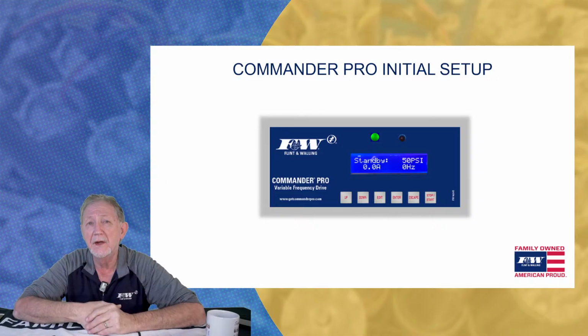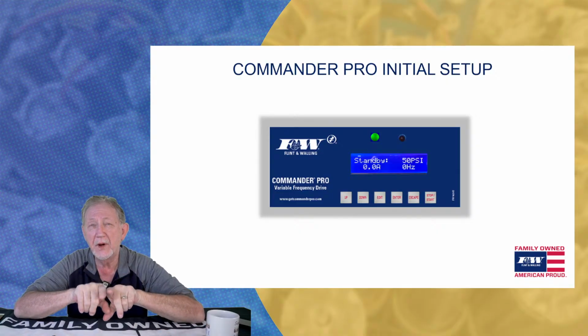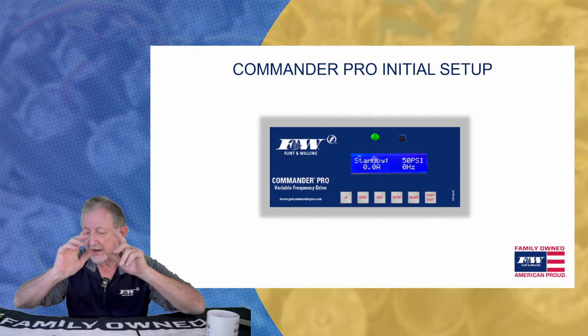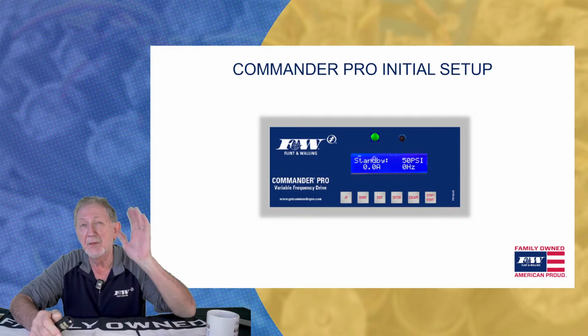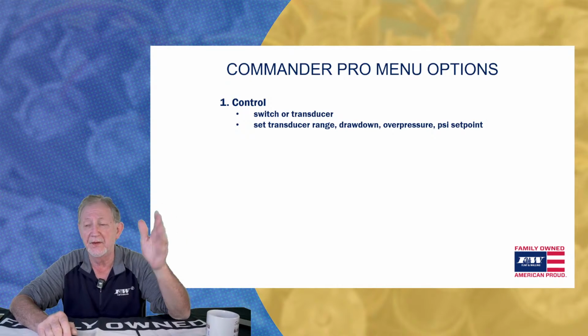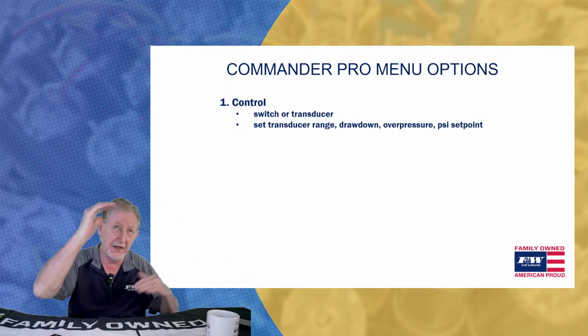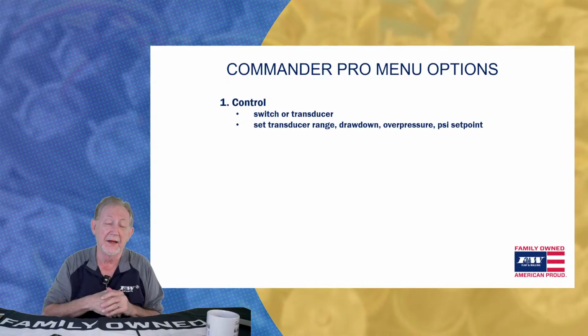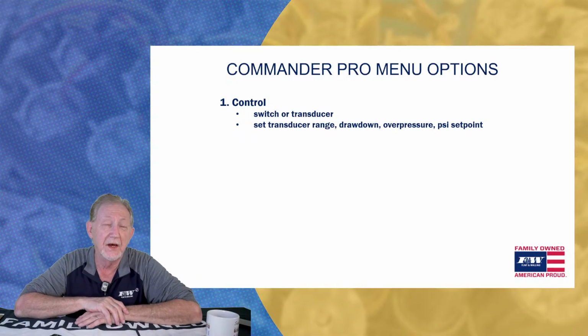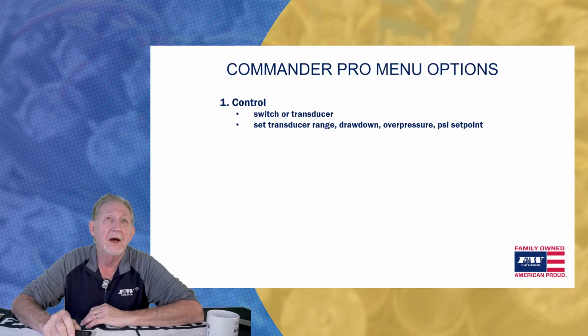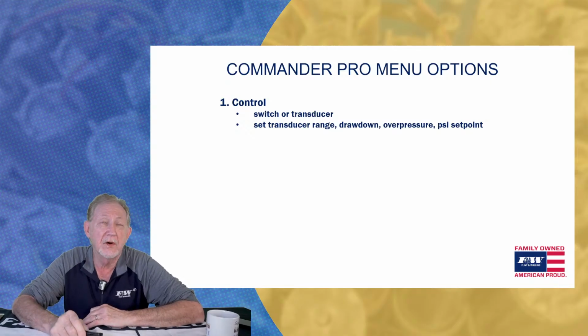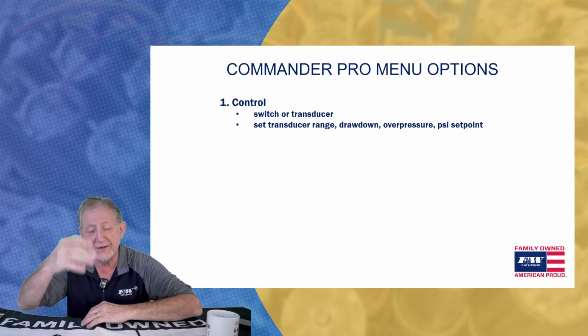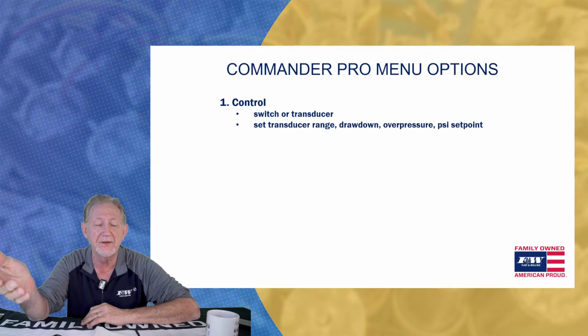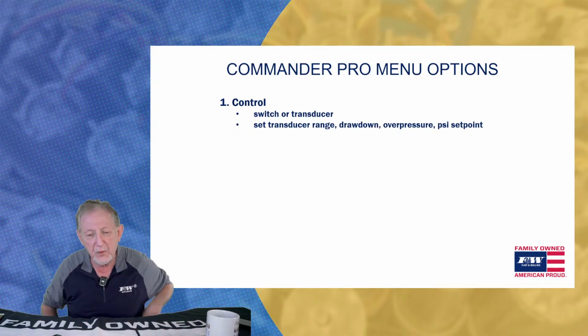From now on, anytime I want to get into this drive, I'm going to have to hit the edit and enter button simultaneously. When I hit that, let me tell you something. There are 10 menus. Not 15, not 20. There are 10 menus in this drive. Let's look at some of these real quick. Number one, control. Are you running a switch or a transducer? If it is a transducer, you're going to set the range, the drawdown and the pressure set point, like we talked about earlier.